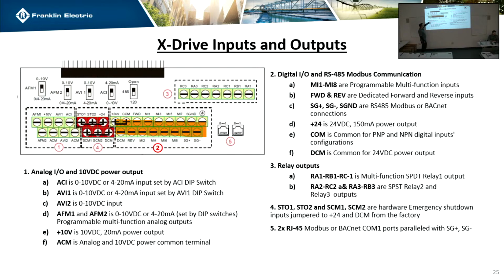So if you ever start a drive, and we'll go over this, but one of the protections is if this is set up to look at that and it doesn't see anything, it will trip. It'll say ACI loss. That's one of the common things you'll see with a panel on startup, is that it's set up to look for this and they haven't wired it in yet. So the very first time you power the drive on, it'll say ACI loss. And it's just telling you that it's looking for something on this input and doesn't see anything.